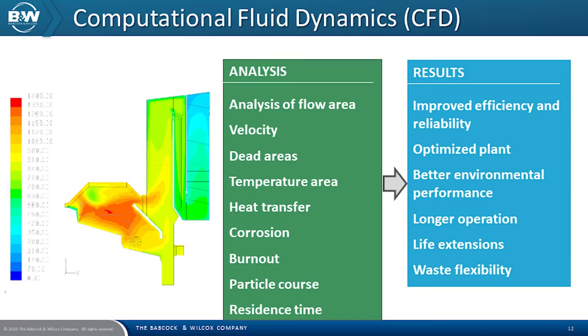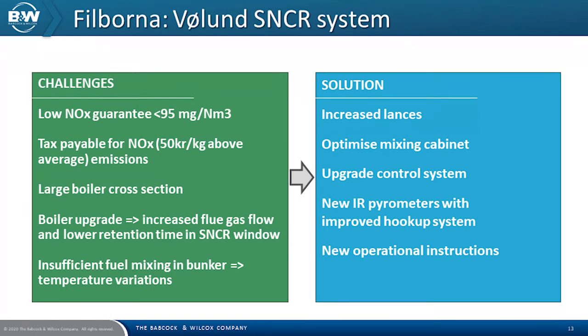One of the key tools our technical team uses when evaluating a plant upgrade is to conduct a CFD analysis. This is an effective method for evaluating design alternatives that would otherwise be too expensive, time-consuming or impossible to test. A CFD analysis provides a detailed representation of the combustion process, flow field and heat transfer. This CFD tool allows us to hit the temperature window we need when modelling it with our Volumix control system. Of course, there are also guarantees for ammonia consumption to consider. In Sweden, there is a tax payable for every kilogram of NOx, so it is desirable to reduce this amount as much as possible. It's rewarded at the end of the year for every kilogram of NOx under the average.